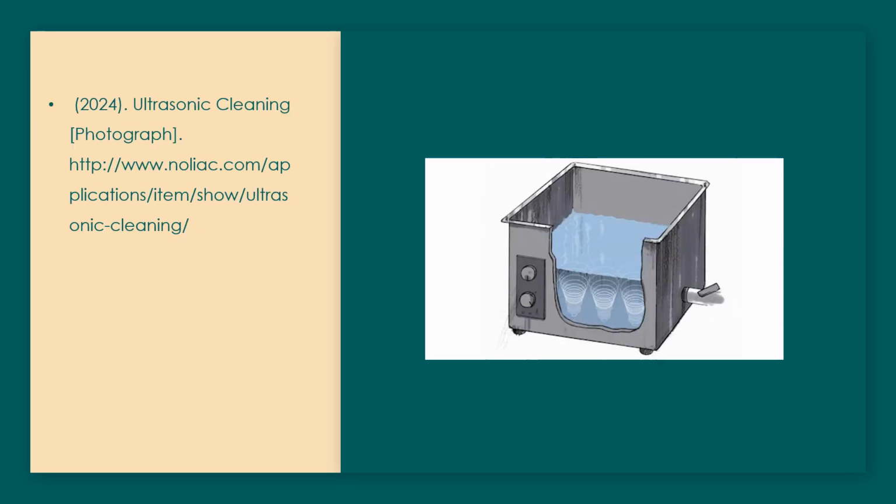Ultrasonic sterilization. This sterilizes through high-frequency sound waves that are transmitted through liquid. This creates cavitation, which will dislodge any contaminants off the instrument. This may take anywhere from 5 to 30 minutes, depending on the instrument that is being cleaned.